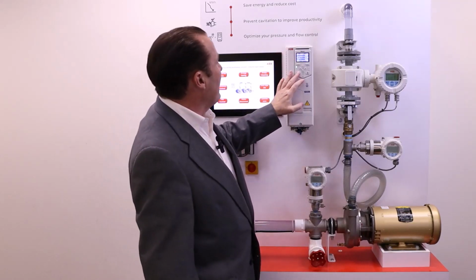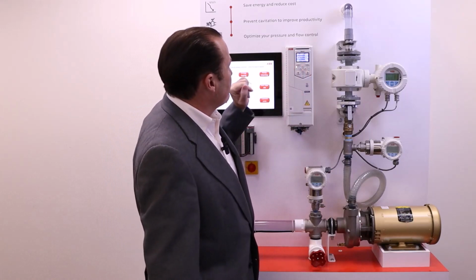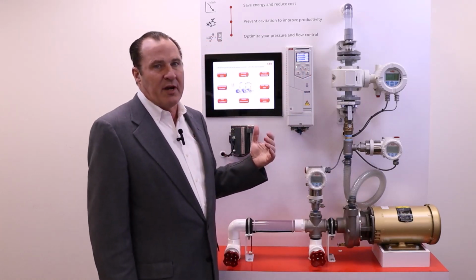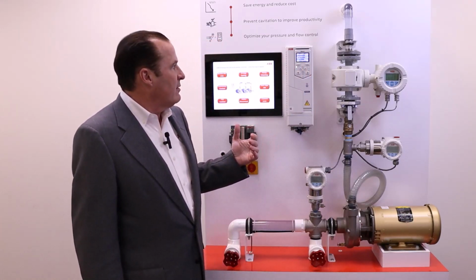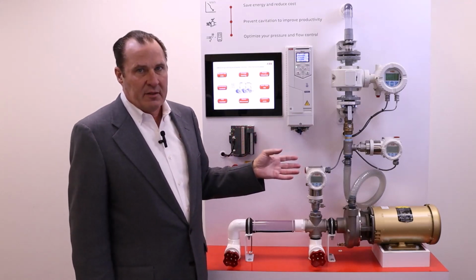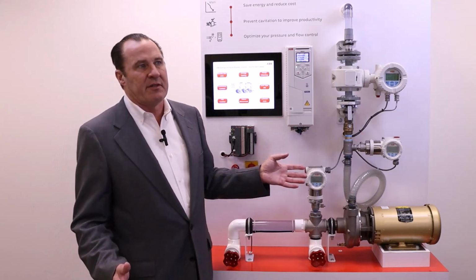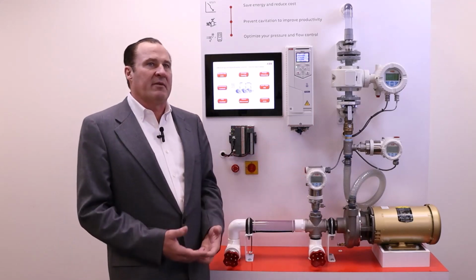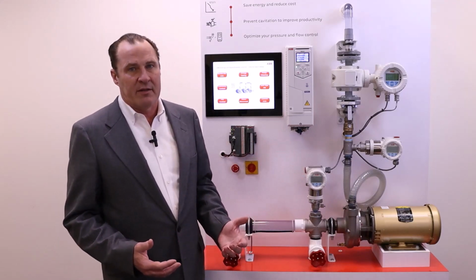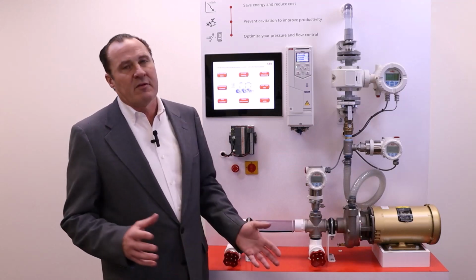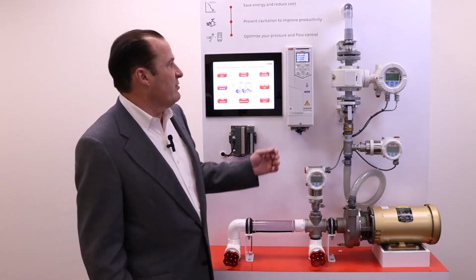I'm going to start the drive up. We got the drive going, and let it stabilize. When you're doing your test in your testing facility, you will need to let the system stabilize. It may have to run for quite a while. In this case here, we're very limited in time, so we'll continue on.